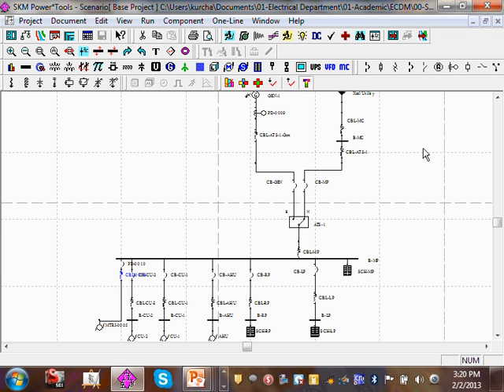And I don't know what wiring method you're going to use, MC cable. Well, I assume if you're going underground, PVC conduit, right? And conductor. That you do is a lot of assumption, and then you change it later on. You see what I mean? But I hear you. So that's the calculation. Any comments, guys? Any questions about that? You don't have to do it twice, so you can size the circuit breaker approximately right the first time anyway.